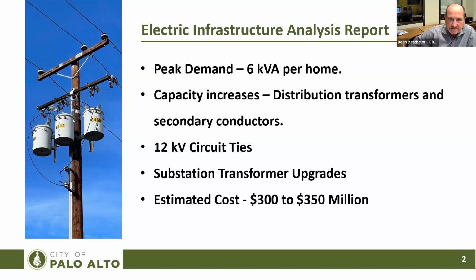One of the things, as I mentioned, distribution transformers and secondary conduit conductors have to be replaced. So those round items sitting on the pole that look something like a garbage can, those are transformers that are up in the air today. We need to make those larger in size so we can get to this peak demand of 6 kVAs. And then also we need to do substation transformer upgrades.